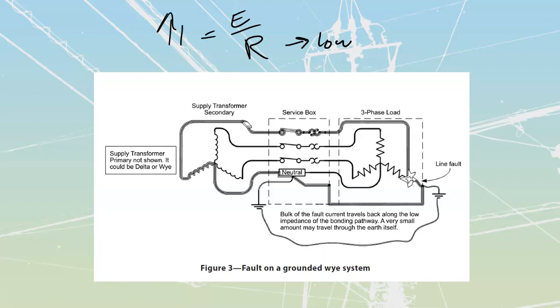So if we take a look at where our grounding options are going to be, they would be either here, at my first neutral inside the service box, that's an applicable ground, or if I don't do that one, I've got the option that instead I could ground it at my neutral on the transformer itself. You have to pick one. You are never, ever, ever allowed to pick two of these. The system can be grounded at either the service box or the transformer, but never both at once. You can refer to CEC 10210A or 10212-1A. That is going to give you clarification for those.